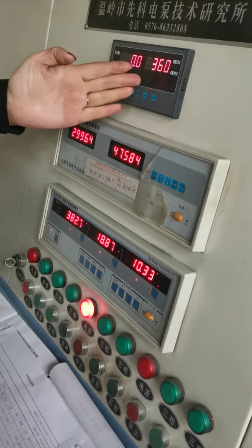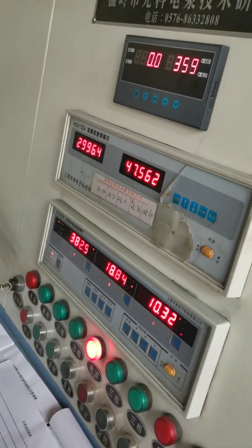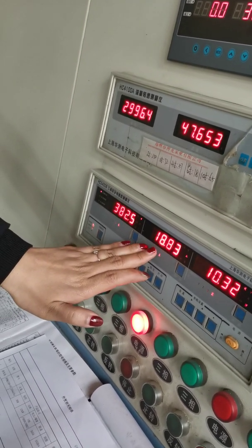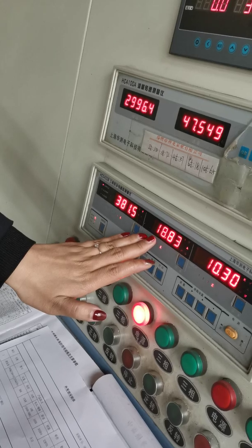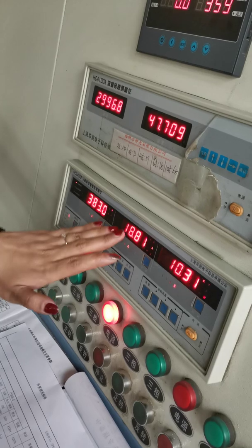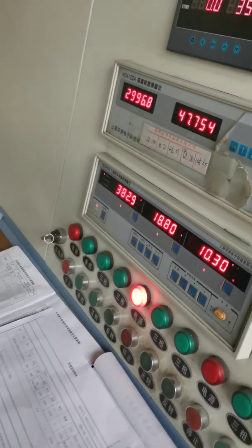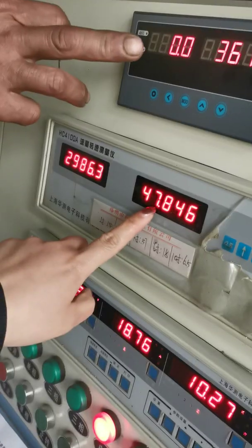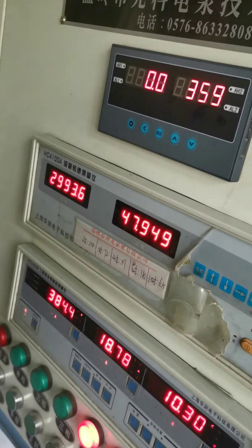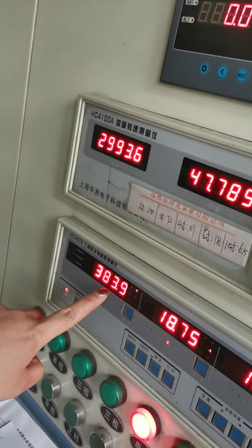You can see the head is 39 meters and the working current is around 10. The rated current of this motor is 21, so the working current is lower than the rated current — this pump is OK. We can see the flow rate is around 50. This is the head, this is the flow rate, and this is the current. The voltage input is 380 volts.